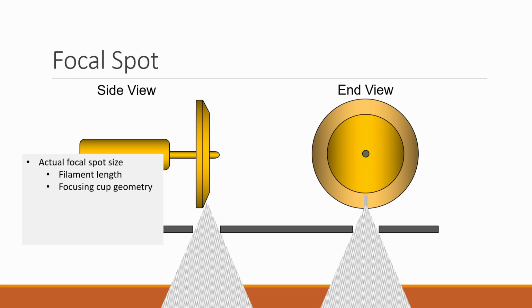It is preferable to have a small focal spot because small focal spots produce finer detail on a finished radiograph. Generally, the price paid for a small focal spot is heat is being concentrated in a smaller area, increasing the chance of pitting or melting of the anode and limiting the mA one can use for technique selection.